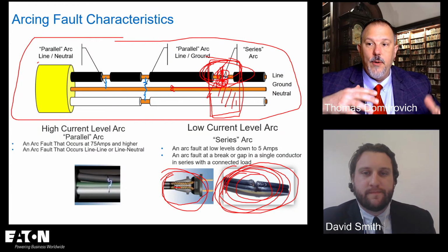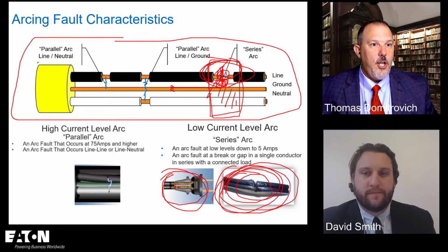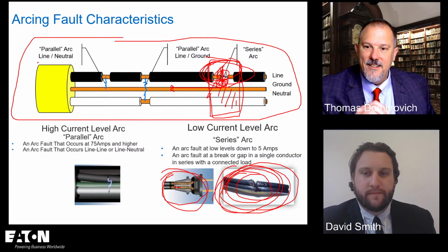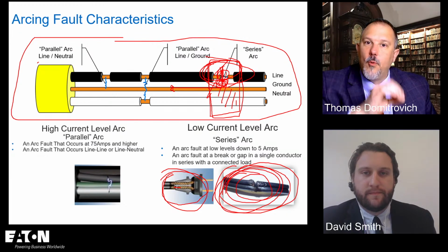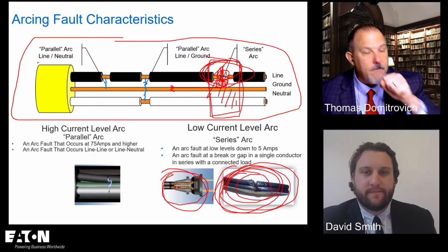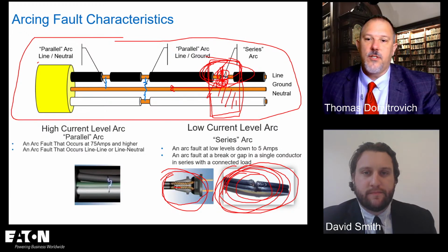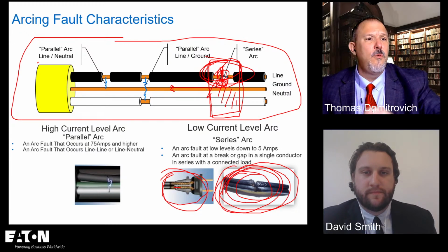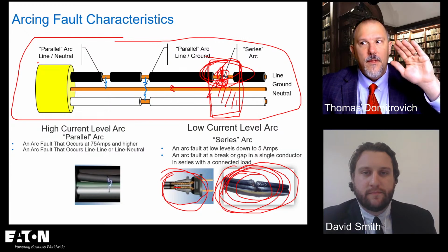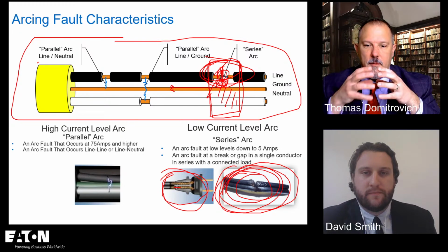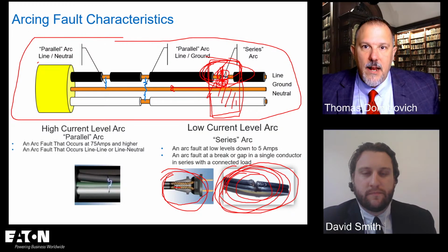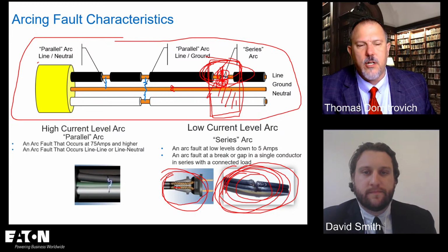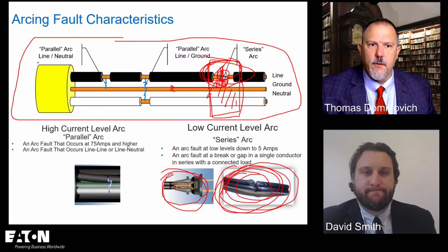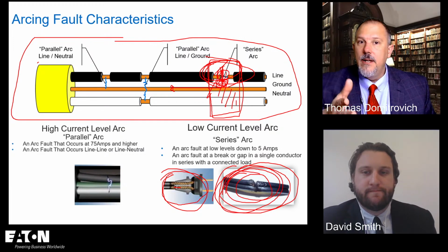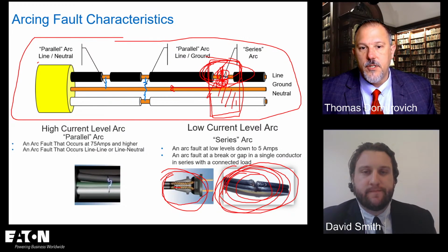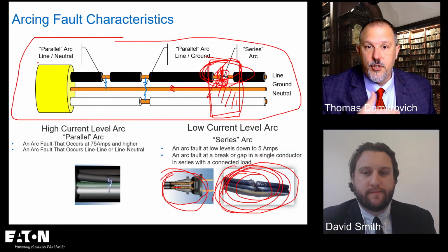So you have all of these things going back and forth, and if you understand a little bit more about the technology, troubleshooting will become a little easier, because now you can look at it through the mind of the AFCI and say, okay, I know series arc is probably what I'm going on, because the 75 amp branch feeder AFCI, tried and true, hardcore, it works. Detecting a 5 amp series arc is a challenge for the microprocessor. It's a challenge for the products that you put on that circuit and all the noise. Dimmer switches caused us a problem in the day. Treadmills with variable frequency drives, all those nasty waveforms. Vacuum sweepers have really nasty looking waveforms. So understanding these details helps you troubleshoot the circuit.